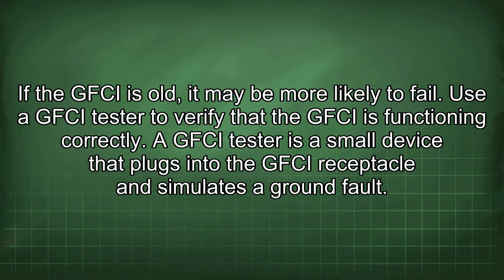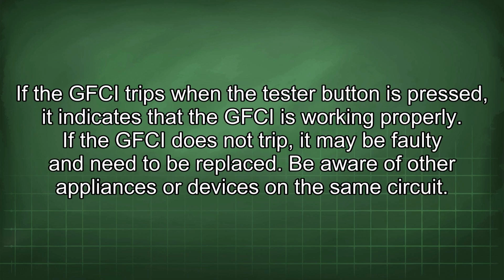Use a GFCI tester to verify that the GFCI is functioning correctly. A GFCI tester is a small device that plugs into the GFCI receptacle and simulates a ground fault. If the GFCI trips when the tester button is pressed, it indicates that the GFCI is working properly. If the GFCI does not trip, it may be faulty and need to be replaced.